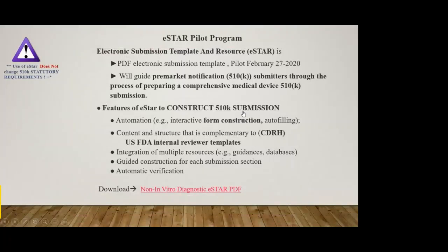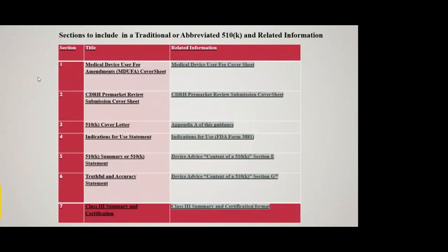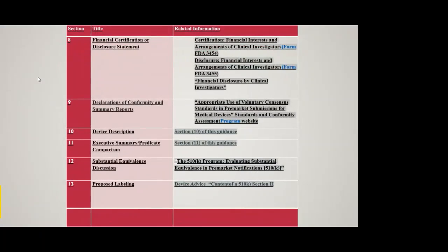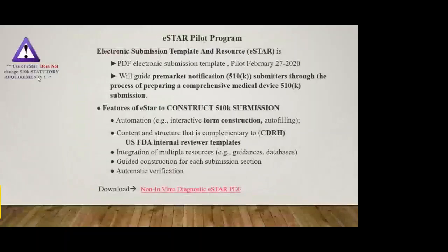So we go to the main topic here, eSTAR. Note the caution here. Use of eSTAR does not change any of these requirements. You're still obligated to go through and make sure these are all available as they pertain to your devices. Obviously, they will vary, whether it's for this gizmo or that gizmo, but it is not a substitute for or a change in the regulations for the FDA.